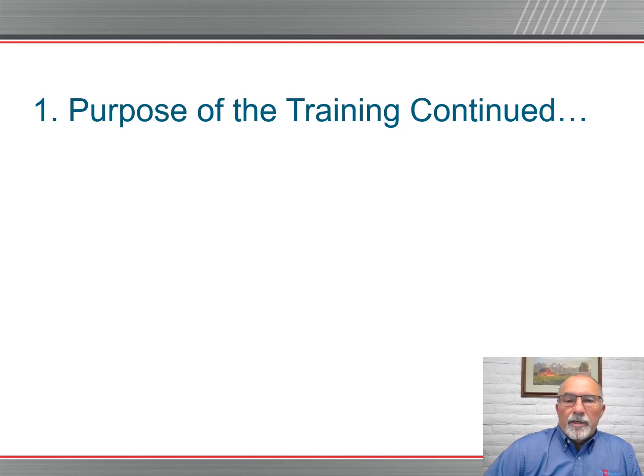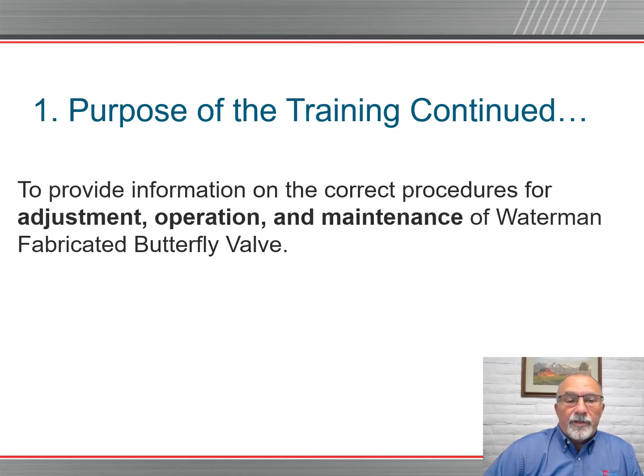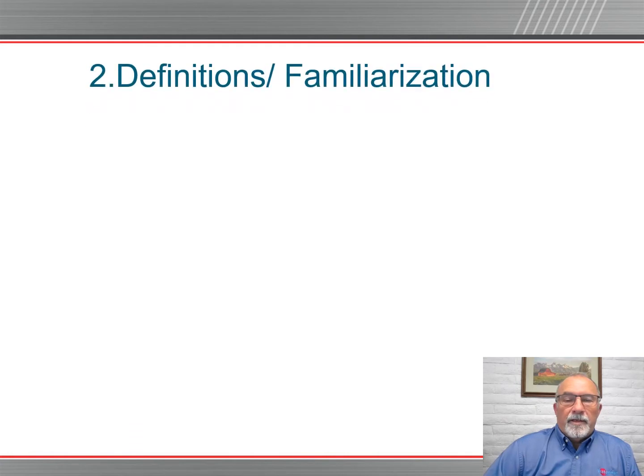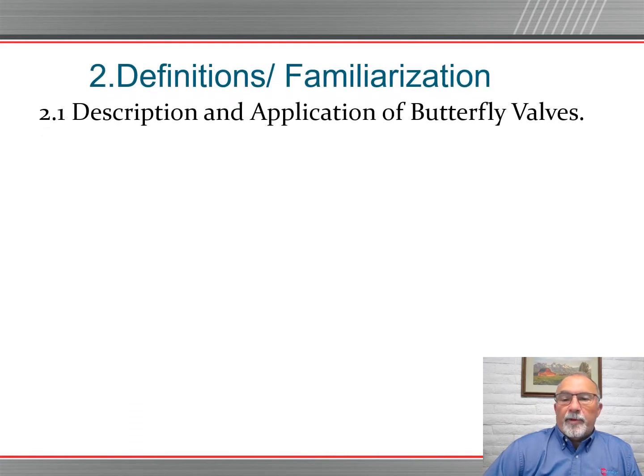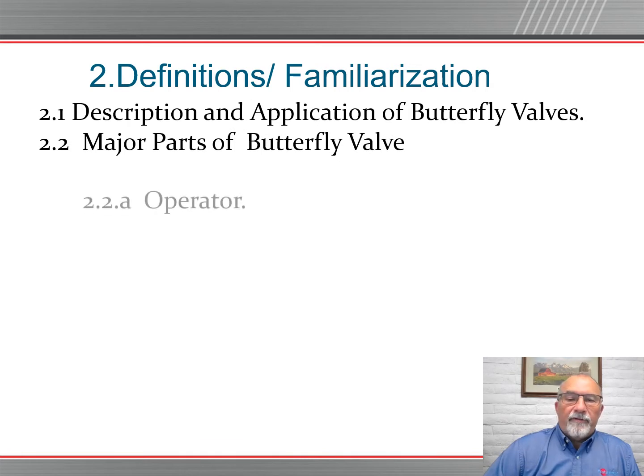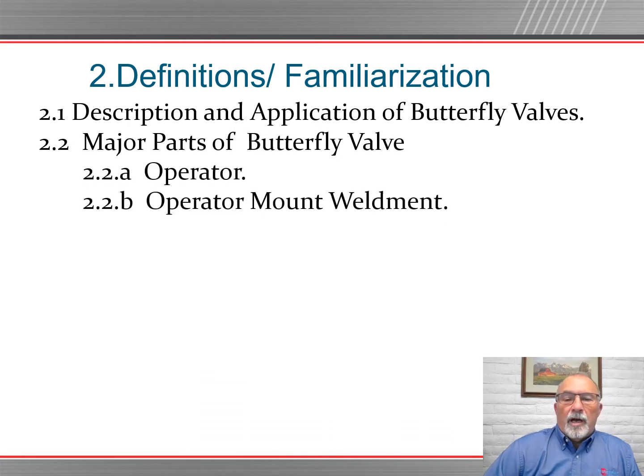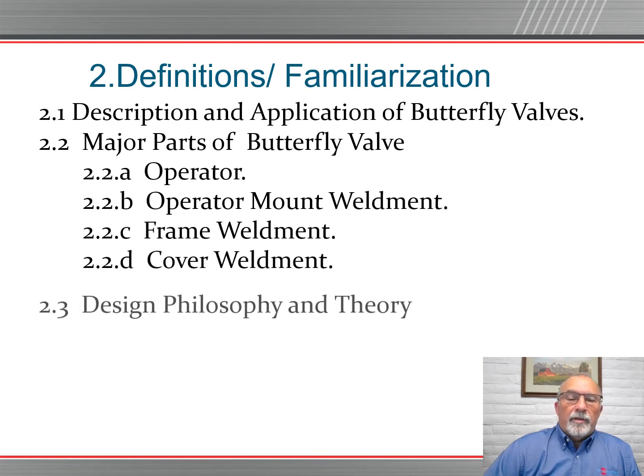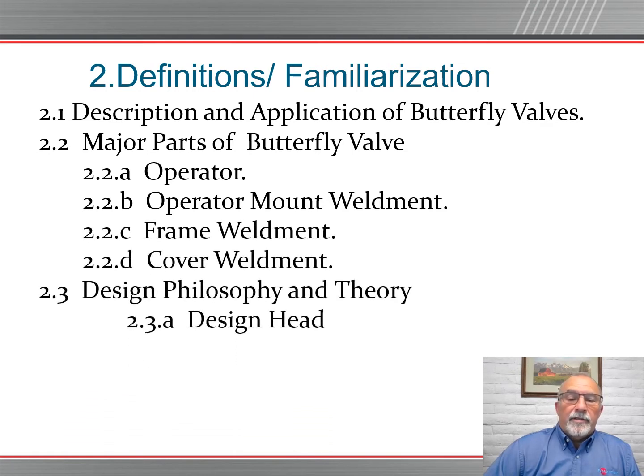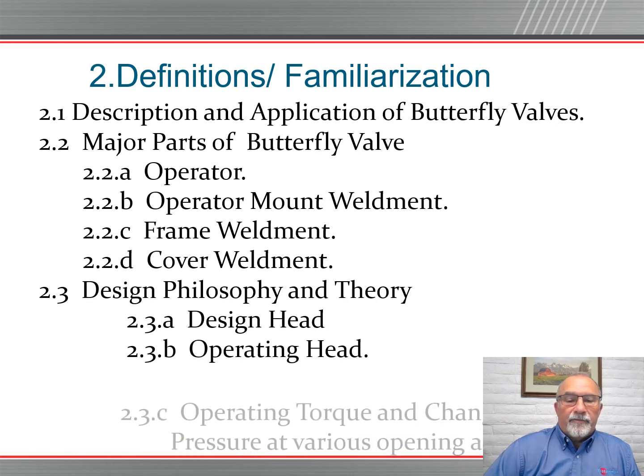Let's get started. The purpose of the training continued in definition is to provide information on the correct procedures for adjustment, operation, and maintenance of Waterman fabricated butterfly valves. Description and application of butterfly valves. Major parts of the butterfly valve are going to be covered: operator mount weldments, frame weldments, cover weldment, design philosophy and theory, design head, operating head, the difference of the two, operating torque and change pressures at various opening angles.